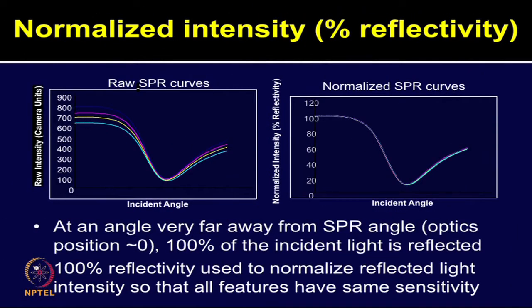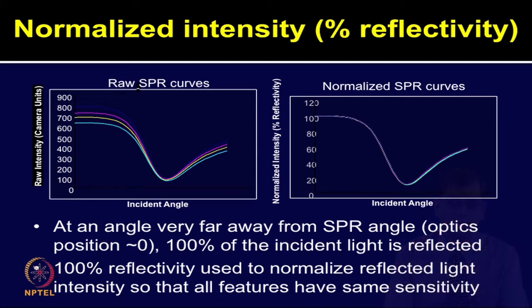The next important step is how to normalize intensity or percentage reflectivity. The left-hand side image shows a raw SPR curve, whereas the right-hand side image shows a normalized SPR curve. At an angle very far away from the SPR angle, with optics position around zero, 100 percent of the incident light is reflected. This 100 percent reflectivity can be used to normalize the reflected light intensity so that all features have uniform sensitivity.